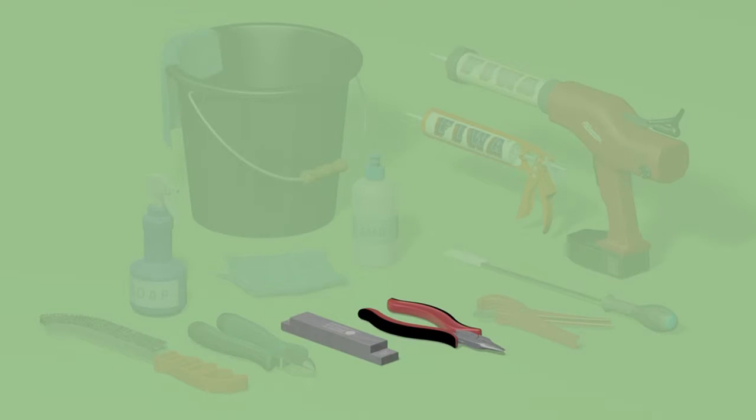Flat nose pliers and an adjuster with a notch of 20 mm are used to adjust the set of filler sleeves, a tube cutter to cut the injection nozzles of the sealant cartridges. To press down the sealant in between cables, a special tool is developed. The head is made out of PTFE, which doesn't stick to the sealant.